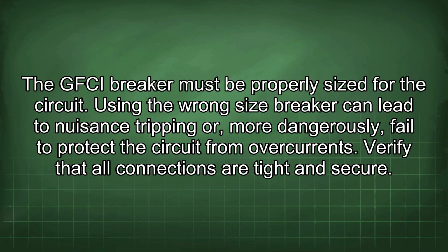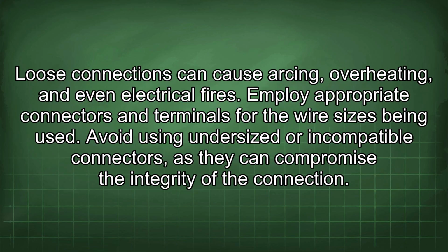Verify that all connections are tight and secure. Loose connections can cause arcing, overheating, and even electrical fires. Employ appropriate connectors and terminals for the wire sizes being used. Avoid using undersized or incompatible connectors, as they can compromise the integrity of the connection.